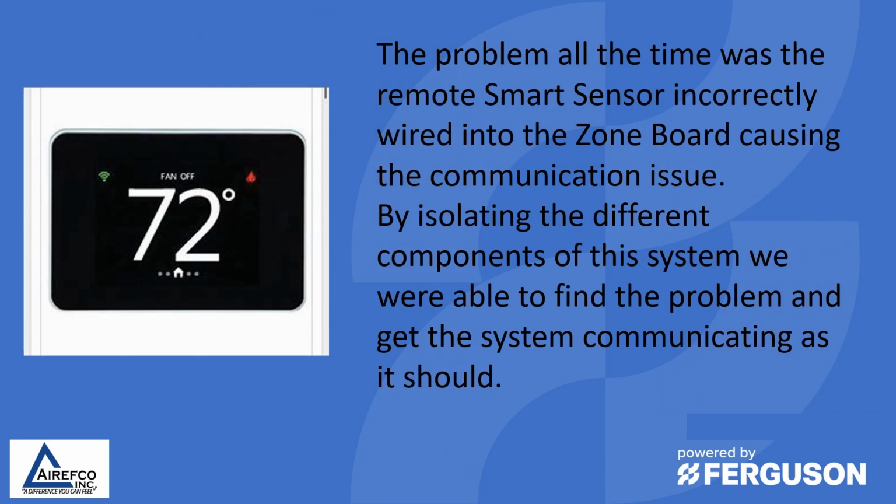So the problem all the time was the remote smart sensor incorrectly wired into the zone board, causing the communication issue. By isolating the different components of this system, we were able to find the problem and get the system communicating as it should.